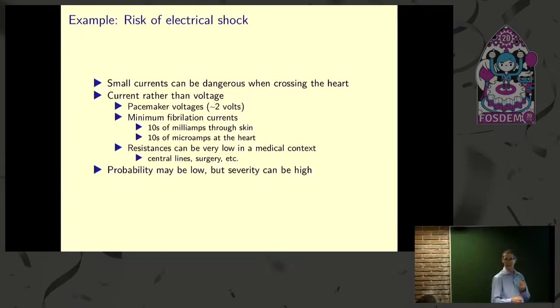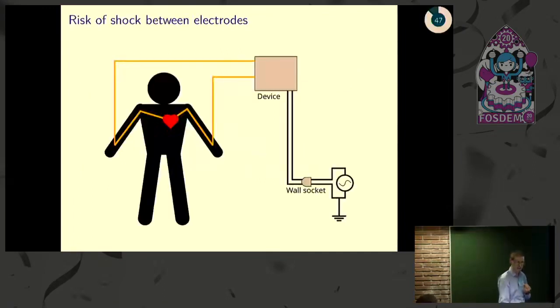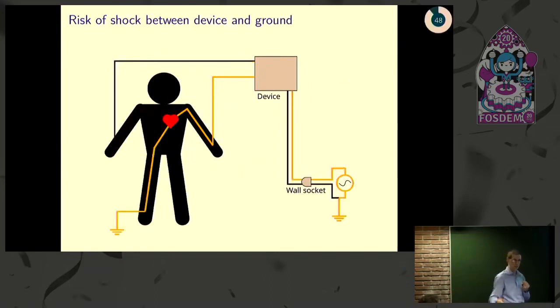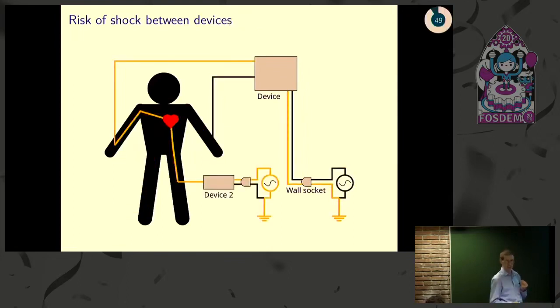If you have an IV in or things like that, you can end up with very low resistances. These can show up in the obvious way, flowing in one electrode in your device through the heart and back out to the other electrode, but it can also be something less obvious, like through an electrode in your device, through your heart, to something like a water faucet you're touching. Or even less obvious, maybe you're hooked up to another device that's malfunctioning, and if your device connects through you to ground, your device can contribute to a shock.